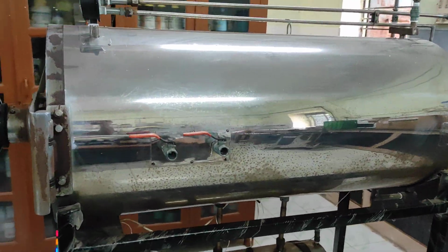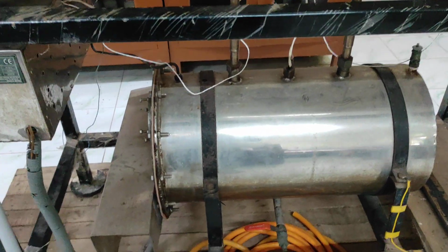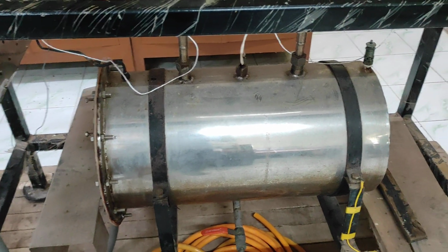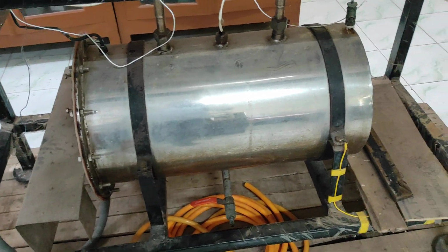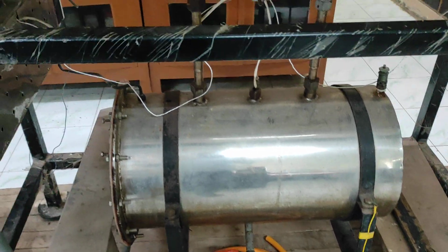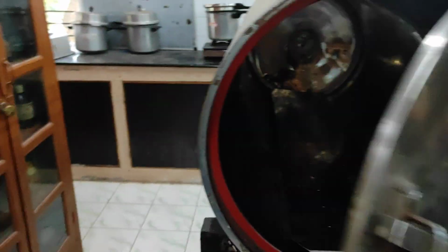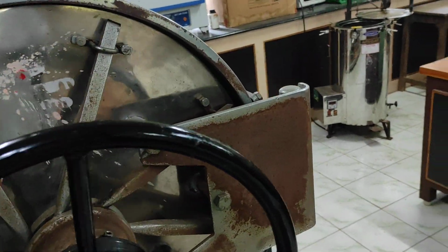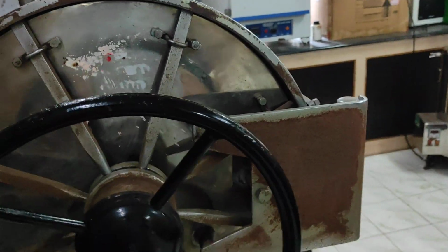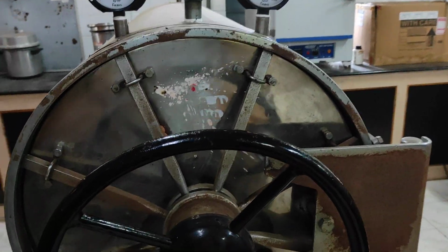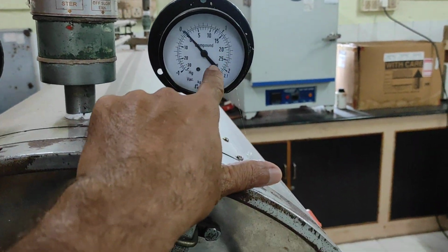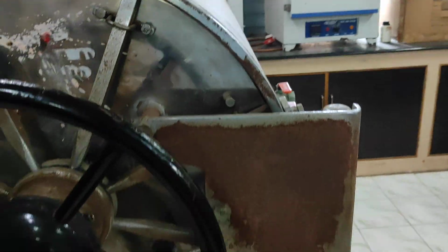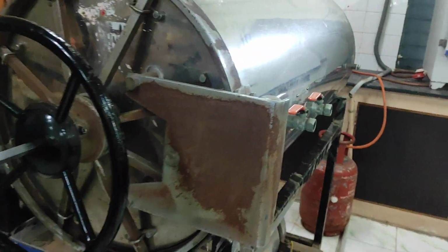So this is the sterilization chamber. This is the boiling chamber. The boiling chamber has rods, heating elements which heat the water. The heated, boiled water produces vapor. The vapor is sent to the sterilization chamber. We keep our medium in this chamber, and then close it tightly like this. Right. Then the sterilization chamber temperature increases. That is visible here. When it reaches 15 pounds, we wait for 15 minutes. Then we can switch it off.